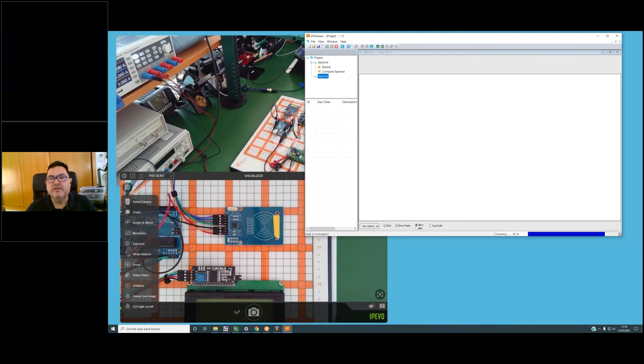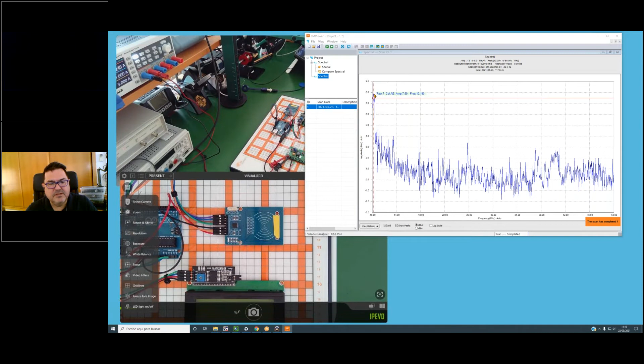Now I have selected all the cells below the device under test, and I start to sweep from 10 megahertz to 50 megahertz. Obviously, this is 13.56 megahertz, so I will be waiting for a first harmonic at that frequency, and probably second and third harmonic of this signal. Additionally, I can find here some noise coming from the digital communications coming to the circuit. So here you can see that I have here the 13.56 megahertz.